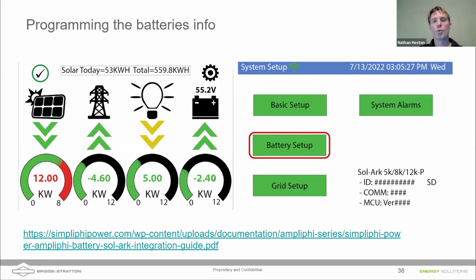And you're exporting or charging the batteries you're sending out of the inverter. So this is from the perspective of the inverter where that energy is going, and those arrows tell you. To do the programming, you will hit the top right corner of the screen. That's where you will get into the setup tab. And once you're in that programming tab, the setup tab, enter battery setup by selecting this button.